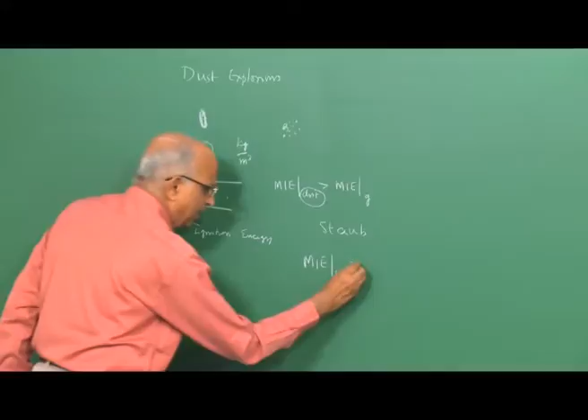Therefore, we say, well, minimum ignition energy of dust is expected to be greater than the minimum ignition energy of the gas. And when we say dust, dust is normally denoted by the symbol ST. The symbol ST comes because a lot of work on dust explosions happened in Germany, and they are pioneers in dust explosions, and dust in German is known as Staub, S-T-A-U-B. Therefore, we show the value of minimum ignition energy, ST meaning dust, is greater than minimum ignition energy for a gas. For the same gas mixture, for the same dust air mixture, the minimum ignition energy for the dust air mixture is greater than for the gas mixture.